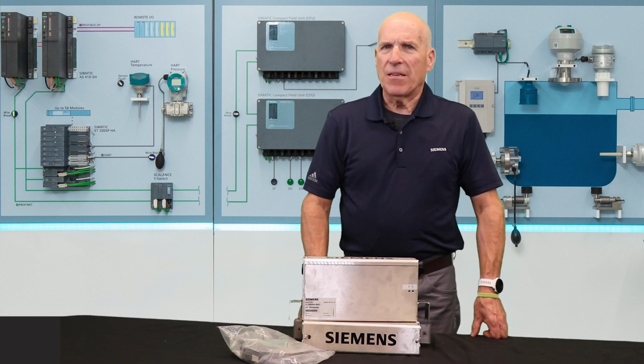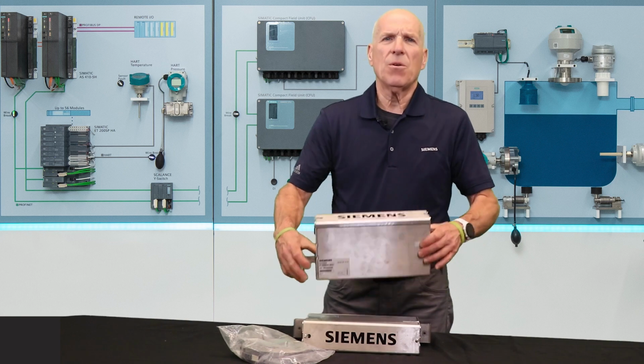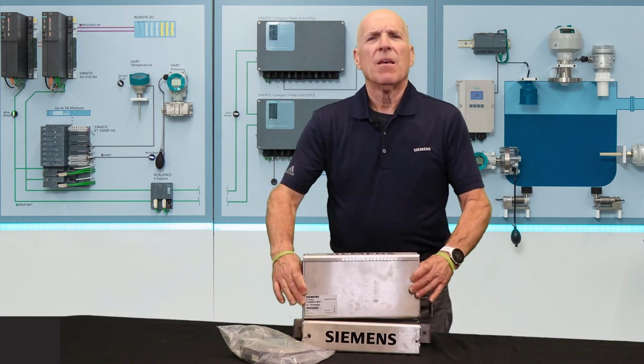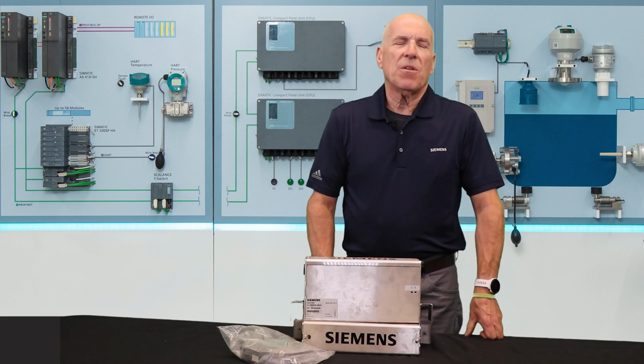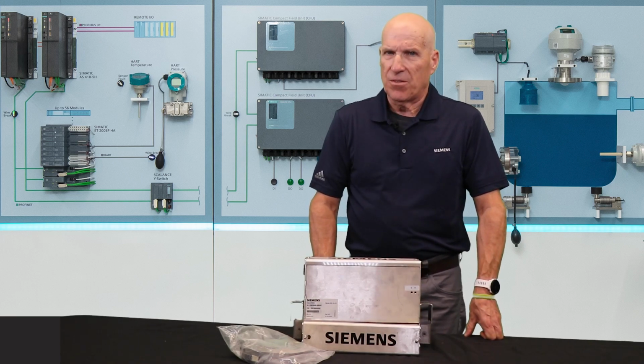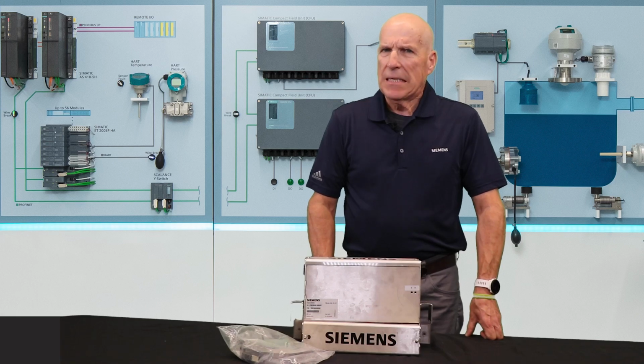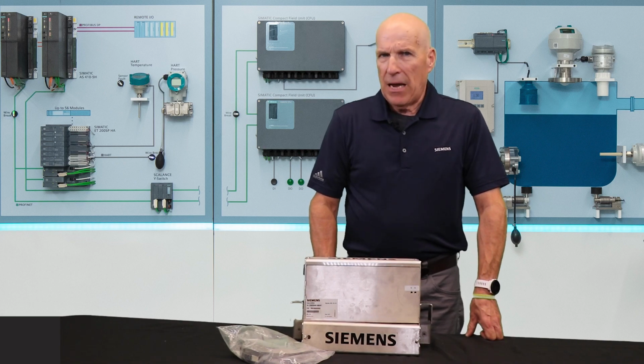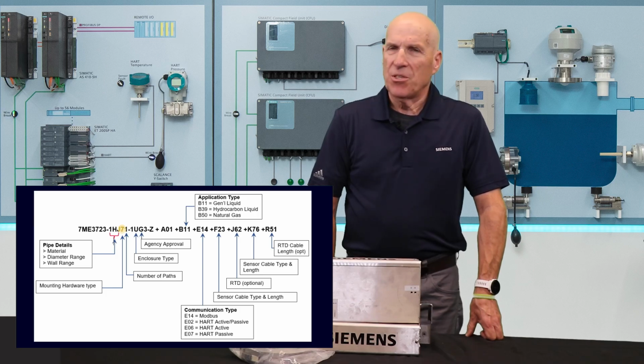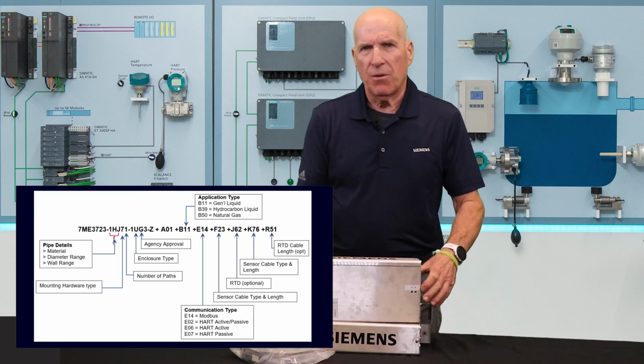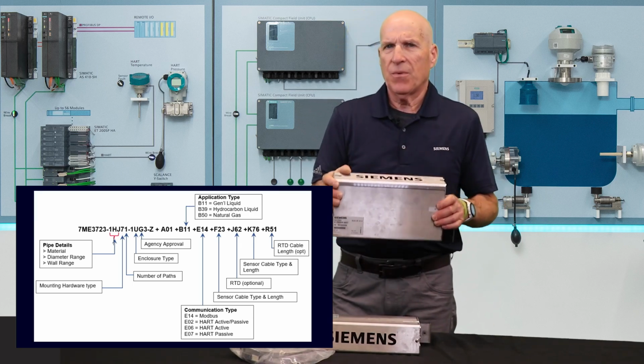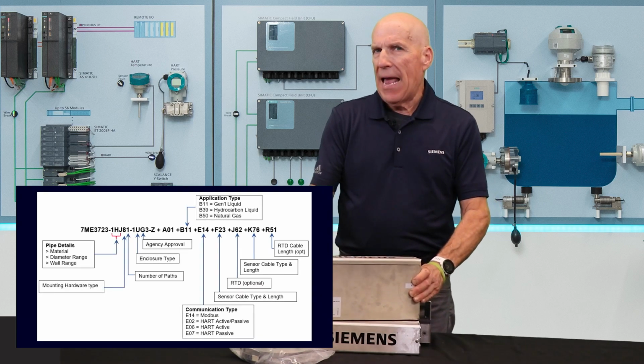As an alternative to standard mounting frames, you may have ordered and received stainless steel enclosures, also known as high precision mounts. These are only suitable for use with C or D size high precision sensors. You'll receive either a single enclosure that houses both sensors if your application is a liquid in a pipe of 8 inches or less. That would be identified by the part number 7 at position 11. Or, if your pipe is larger, you'll receive a 2-part enclosure that each houses a single sensor, which would be identified by the number 8 in position 11.